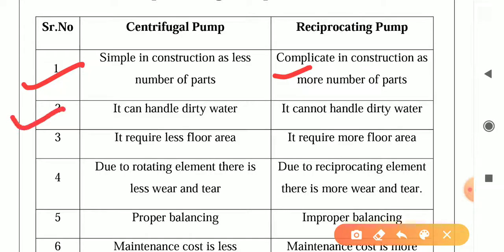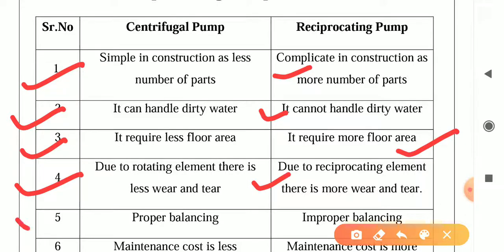Centrifugal pump can handle dirty water; reciprocating pump cannot handle dirty water. Centrifugal pump requires less floor area; reciprocating pump requires more floor area. Due to rotating element in centrifugal pump, there is less wear and tear. In centrifugal pump, there is proper balancing.